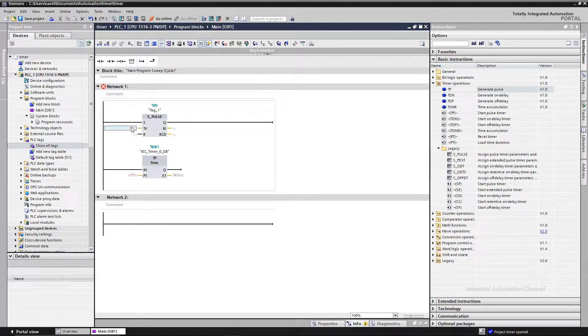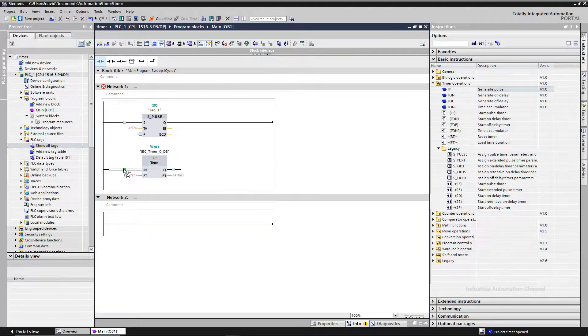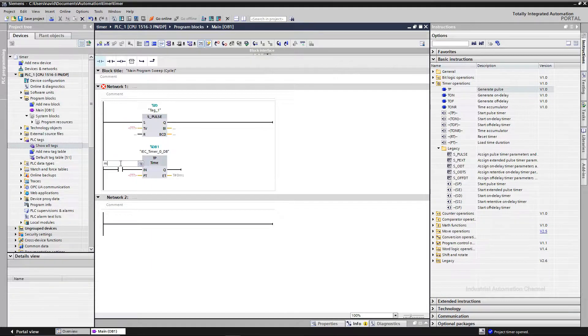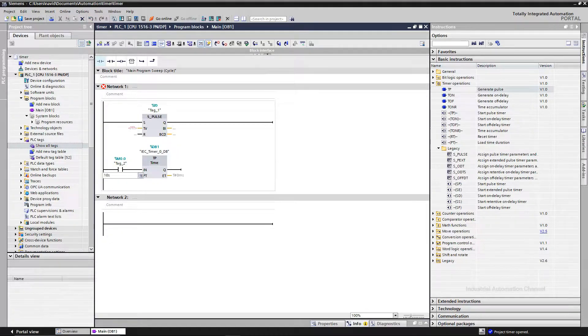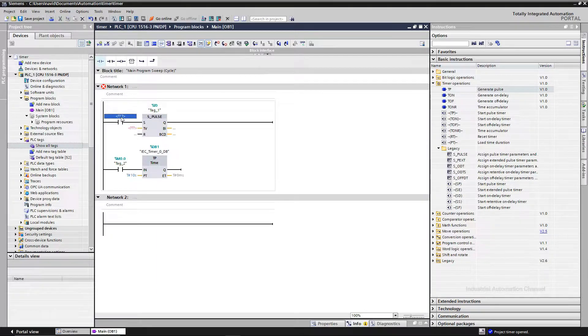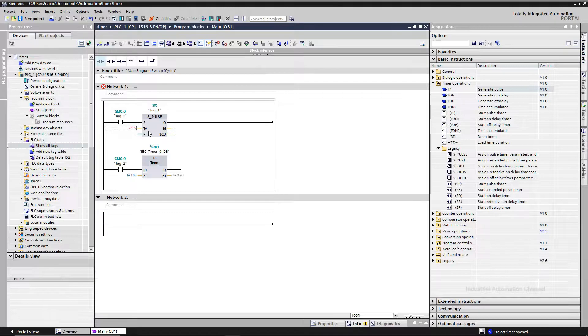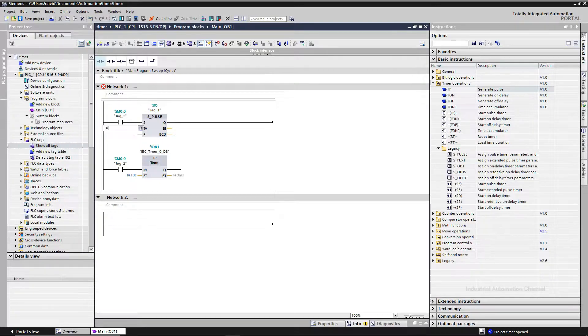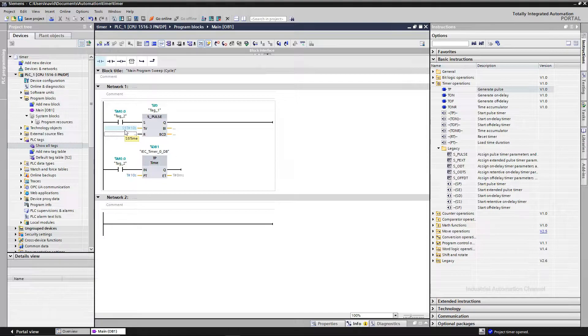As you see, the PLC timer needs two inputs. PT is the preset time and the time duration of the timer. But the S_PULSE timer has three inputs. S is for the start. I insert the contact. When M0.0 is changed from 0 to 1, the timer starts. TV is timer value. And like PT, it's the time that timer will count after activating. I set this time to 10 seconds. So I write 10S. Press Enter. You see here it's written S5. It indicates that this timer is a S5 format timer. R is reset input.